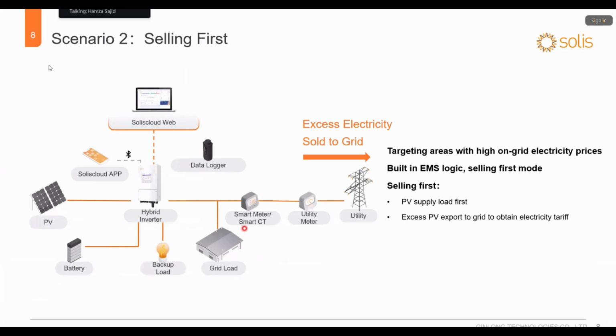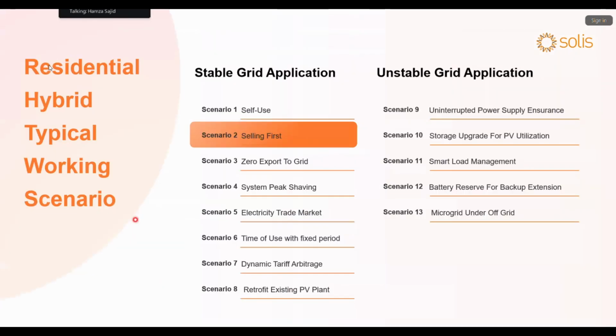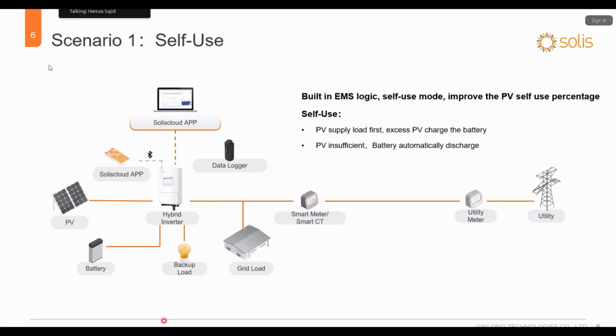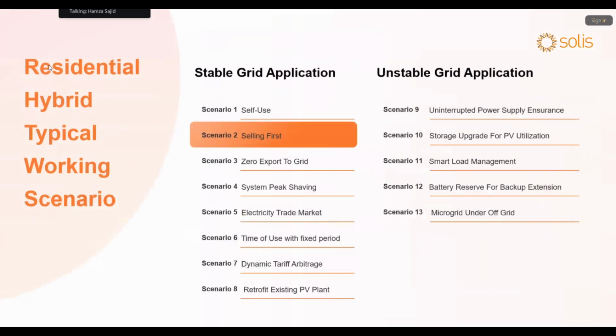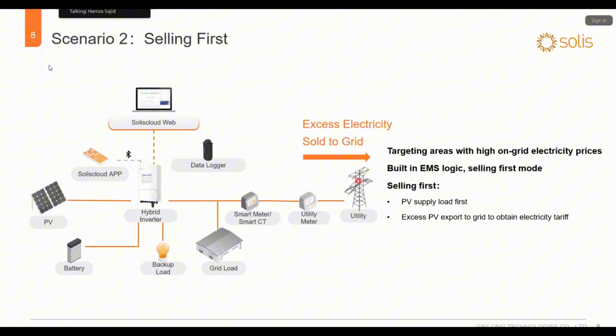Selling first. Okay, this is going to be more useful for, I think, the Sri Lankan market. In this mode, the first priority is to supply the load at the backup load or the gen port load. If there is more supply available from the PV, it is going to go back to the grid. And if there is a specific voltage or SOC for the battery that you can confirm, the inverter will charge the battery to a certain limit, but its priority will be to sell first. So in the self-use, the priority was load first, then battery, and then the grid. In selling first, load first, export back to grid on the second priority, and the third priority will be for the battery.